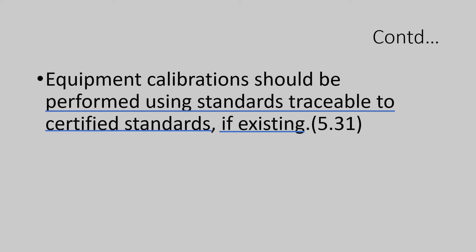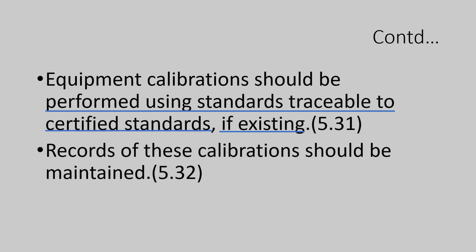Similarly, when you calibrate a weighing scale, the standard weights definitely have to be calibrated with a traceable standard. The traceable standard could be a local statutory metrology department standard — it is a statutory requirement also. As objective evidence, a certificate of compliance is issued by the department, and this has to be renewed every year. Similarly, when you calibrate a pressure gauge or a temperature probe, you have to calibrate with a valid traceable standard. Valid means the traceable standard should be within the next calibration due date.